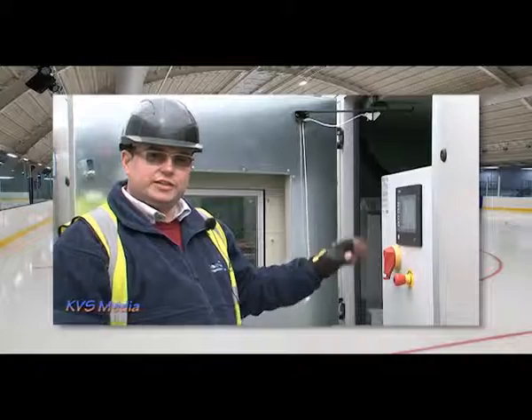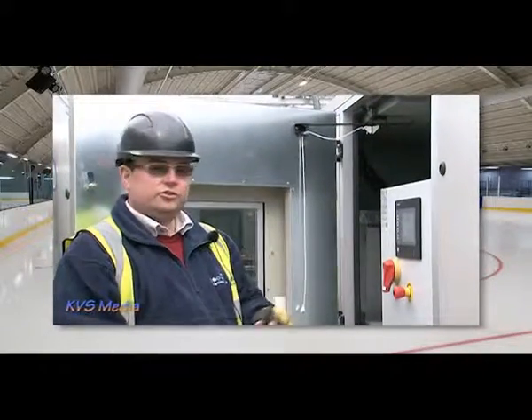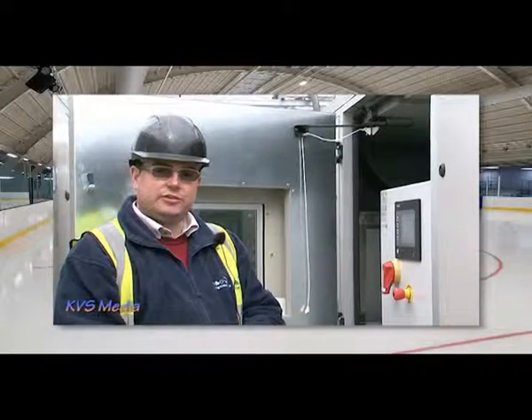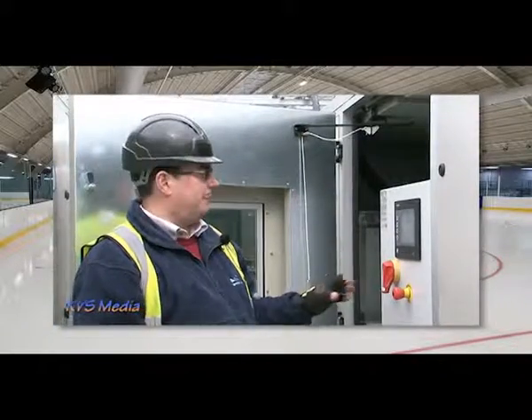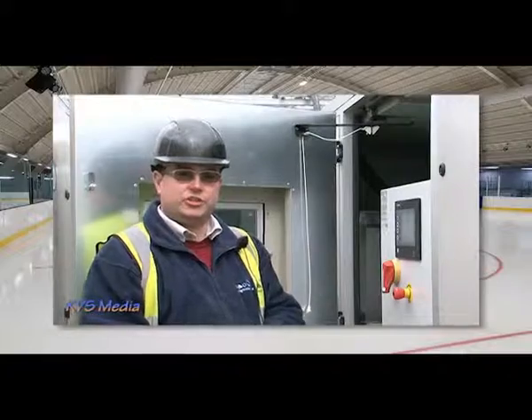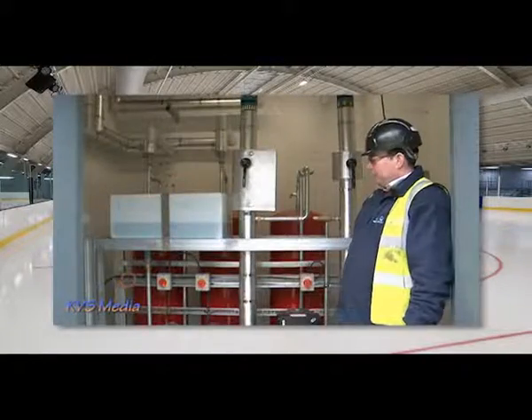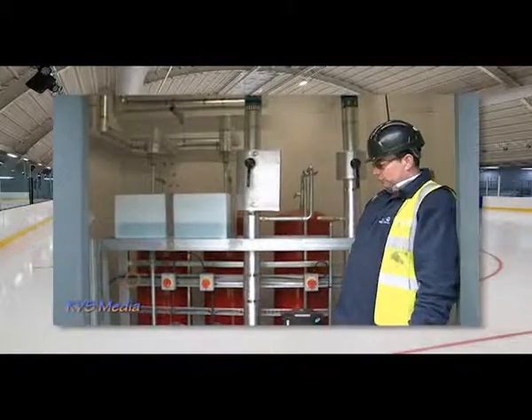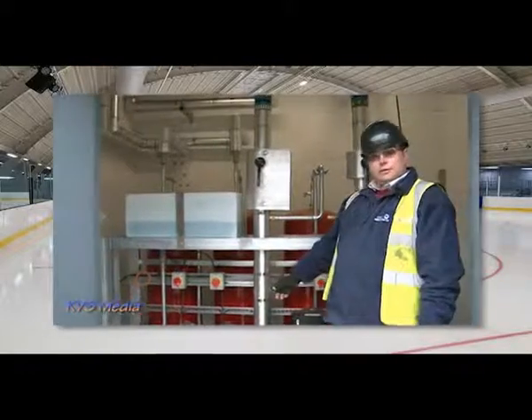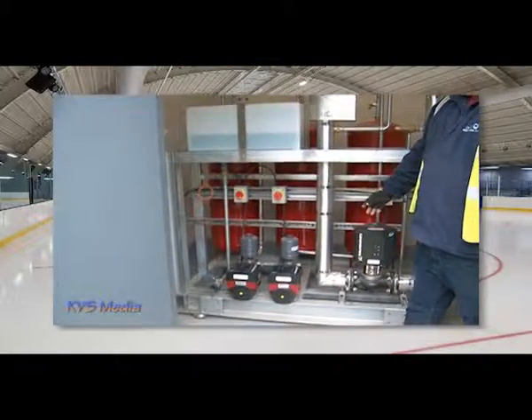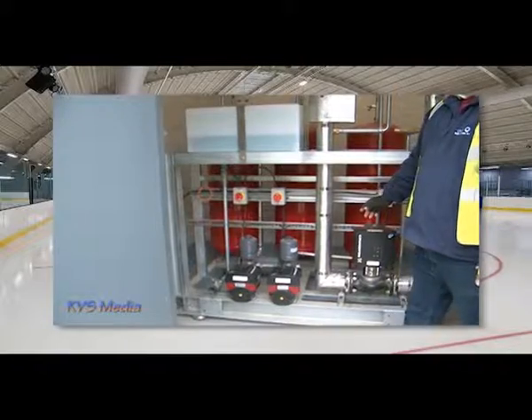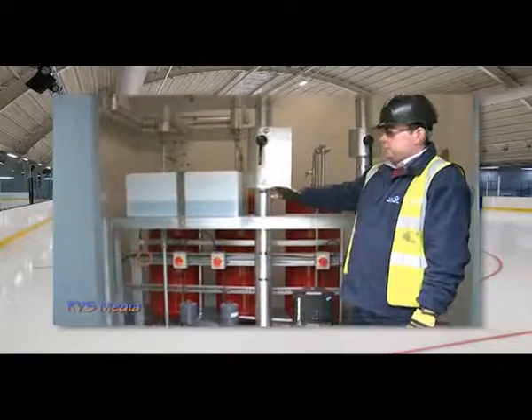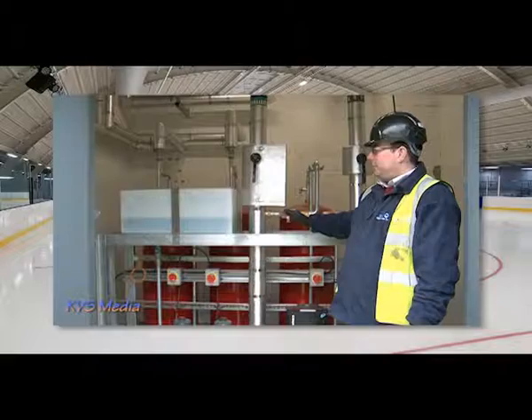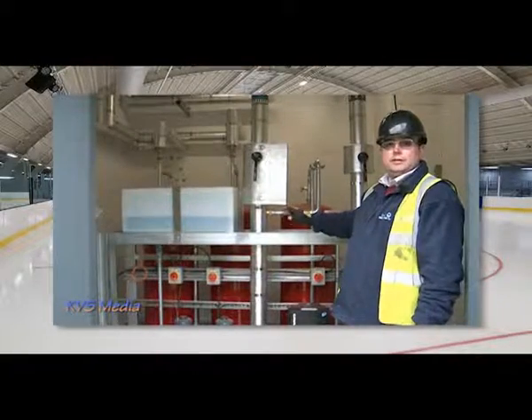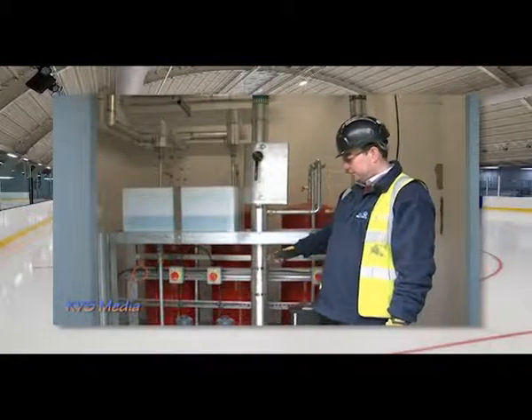Most of the operation takes place in the first floor plant room, which can control and repeats everything that you can see on this screen. These screens are primarily for the engineers' operations during service and maintenance. In here we have the pressurisation pumps for the cold and chill down here on the left, and we also have a hot glycol pressurisation pump down here, consisting of a header tank here which is for glycol mixing and glycol storage, which feeds these header tanks.